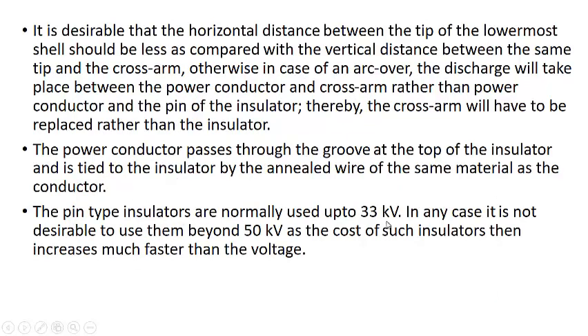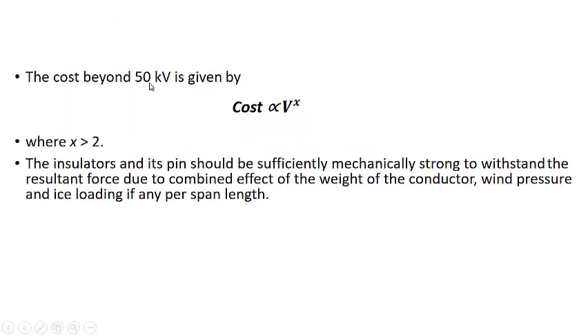Pin type insulators are normally used up to 33 kV. In any case, it is not desirable to use them beyond 50 kV, as the cost of such insulators increases much faster than the voltage. So the cost beyond 50 kV is given by cost proportional to V raised to the power x, where x is greater than 2, or even if x is equal to 2, the cost will be very high. For 11 kV maybe the cost is, let us say, 1000 rupees. For 33 kV the cost may be 3000, but for 120 or 220 kV it may not be 22,000, it may be more than that, 44,000, 50,000, depending upon the value of x. So this is avoided. We don't use the pin type insulator beyond 50 or 33 kV. We go for other types of insulators.